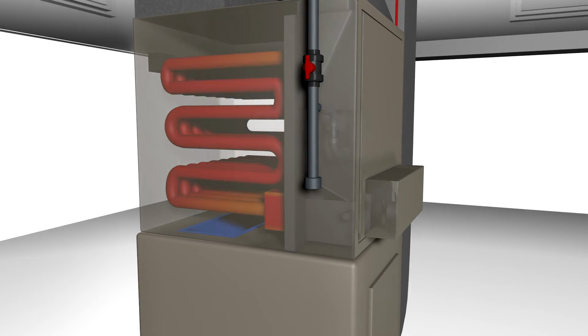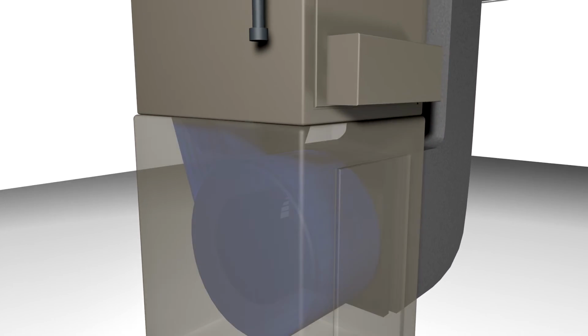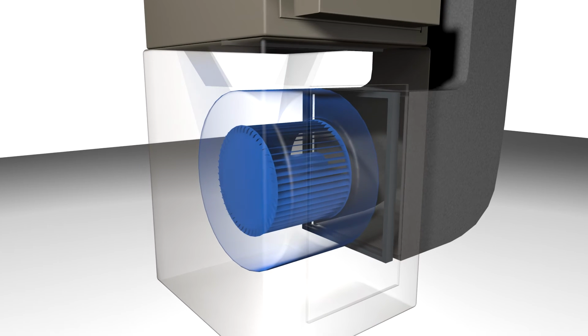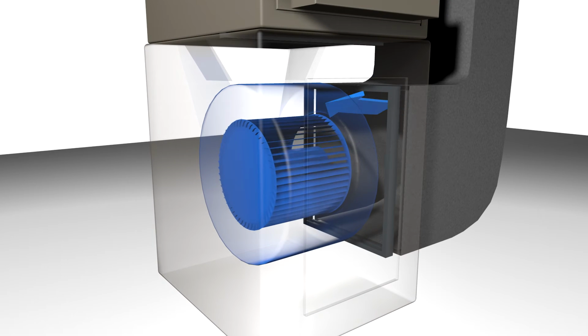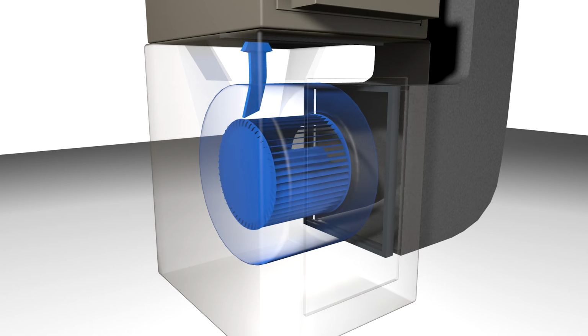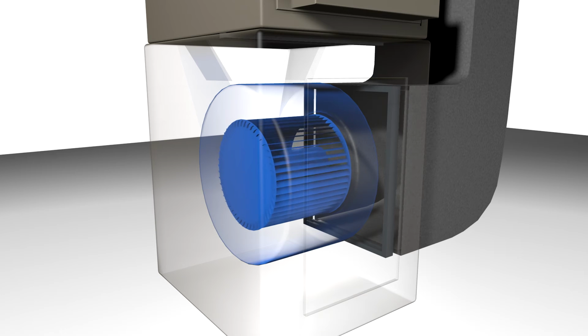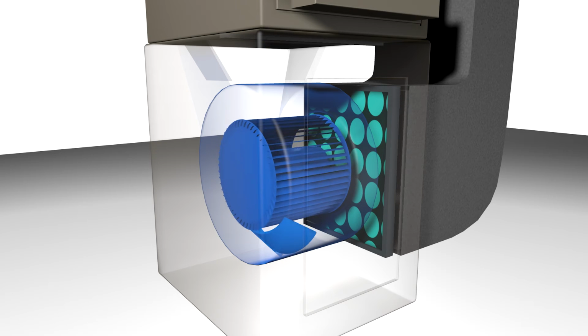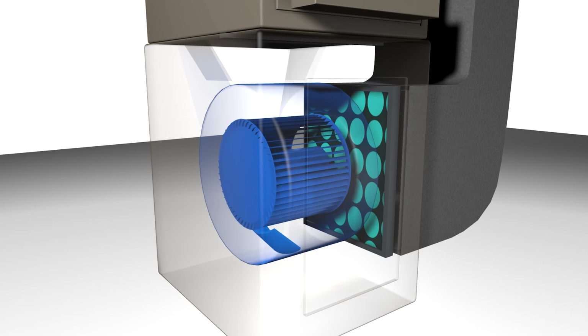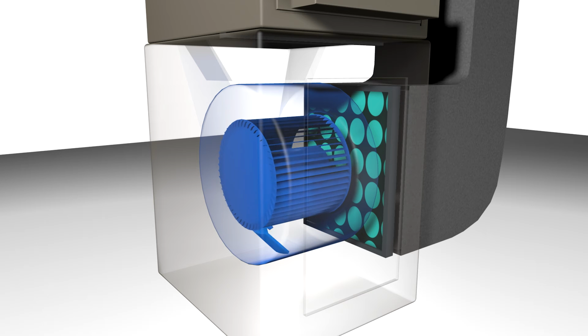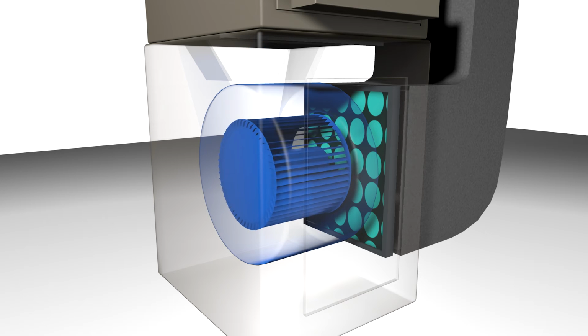The blower fan is the component that moves air coming into the unit from the cold air return ducts into the heat exchanger. It also forces the heated air throughout the ducts and registers of your home. Most high-efficiency units have a variable speed blower that can self-adjust fan speed during operation. The air filter that you replace periodically on your furnace works in conjunction with the blower, helping to keep the majority of dirt and contaminants from entering the furnace and damaging it, or making it less efficient.